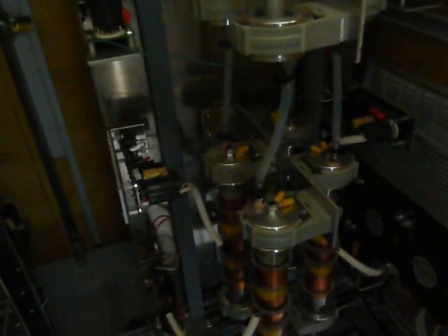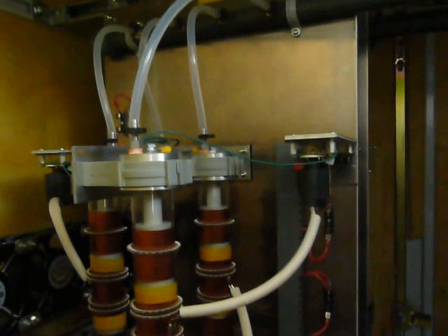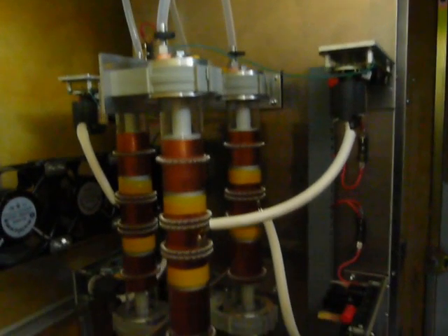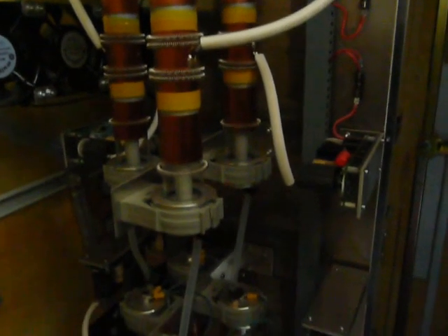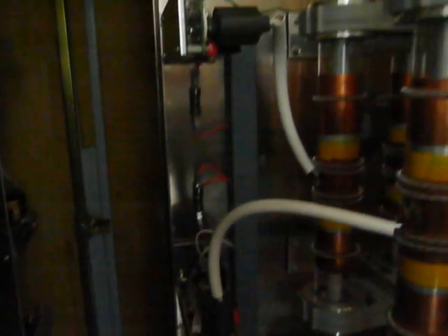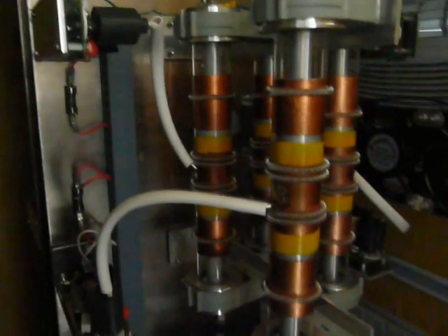And we have several of them throughout the ozone generator. In this specific case, we have 16 lamps and 16 power supplies on this side, and we have the same thing on the other side of the enclosure. This allows for very reliable performance of the ozone generator, as should something happen, the chances that 100% of the ozone production capacity will be lost are very, very slim.